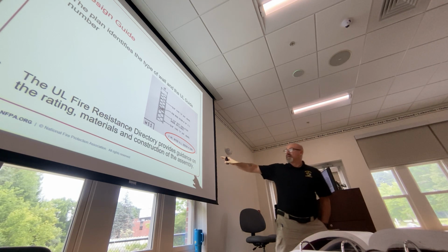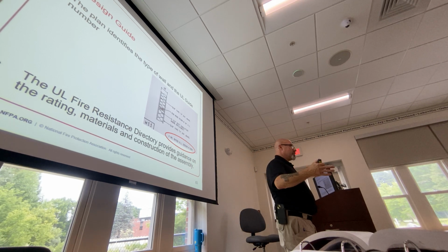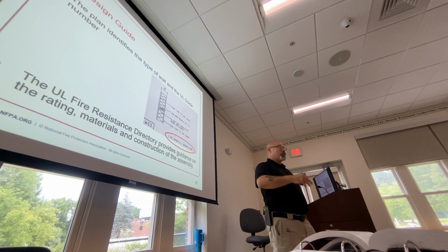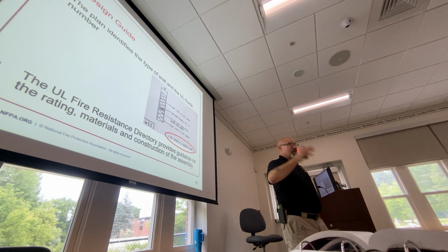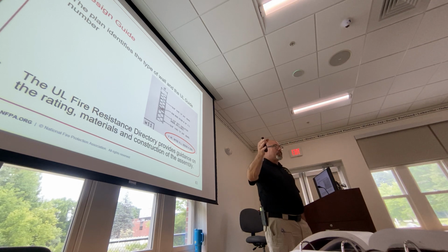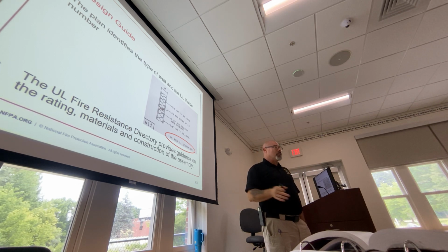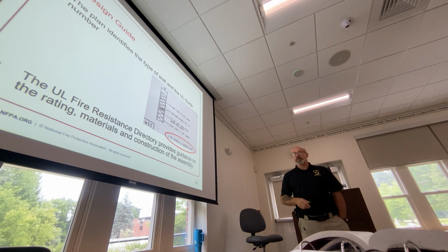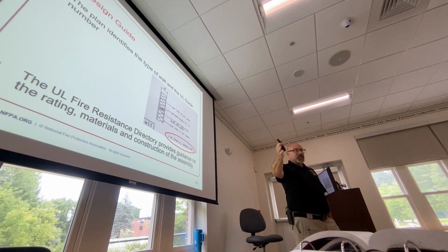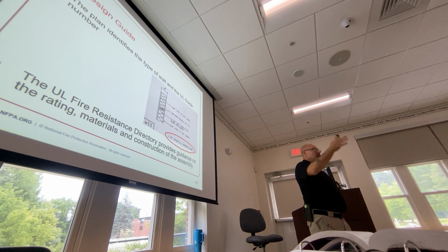When you have this UL design, UL actually has done testing. They put it in a blast furnace, they put flames and heat on it for a certain period of time. Then they take it out and they spray it with a hose stream at 50 PSI. They do the same thing over and over again for all the different assemblies. The process stays the same. All of the criteria remains the same, so that way it's equal. If I'm testing this product versus this product versus this product for a 1-hour rating, this is how we're gonna do it.